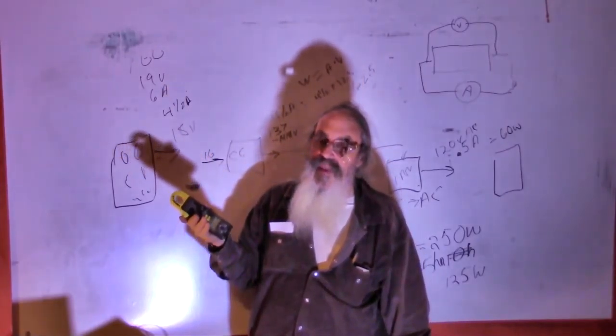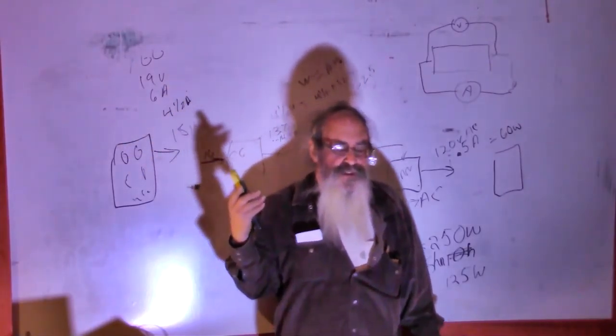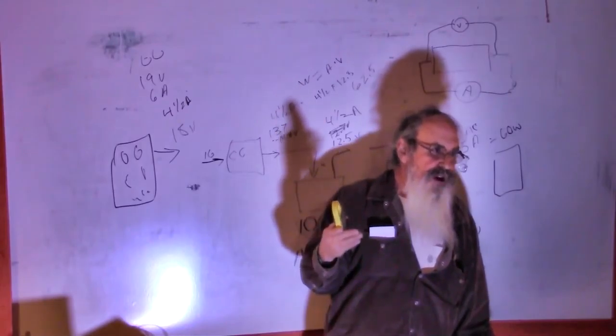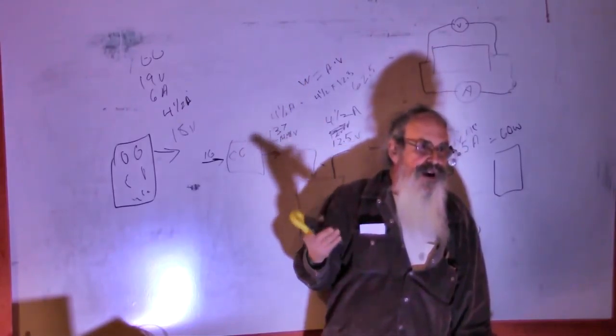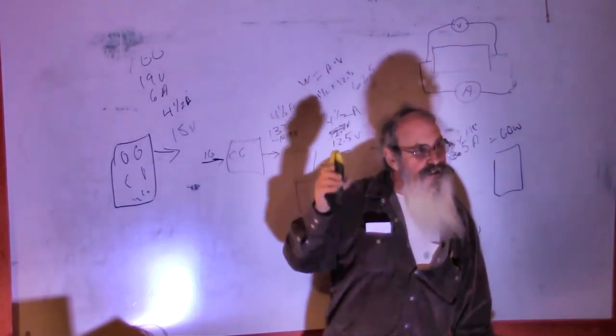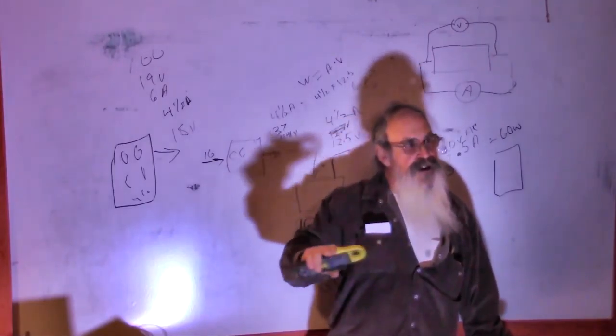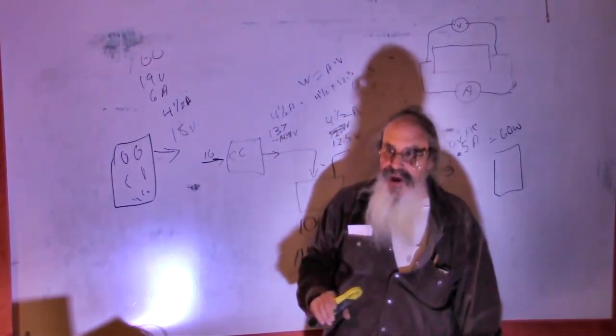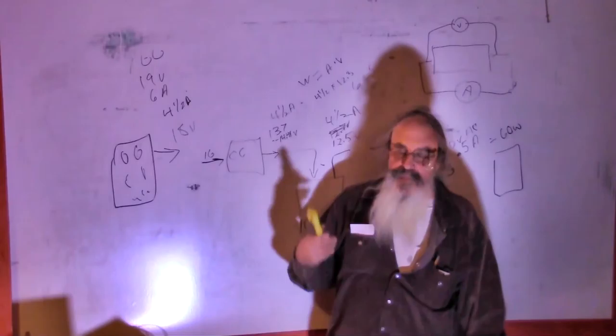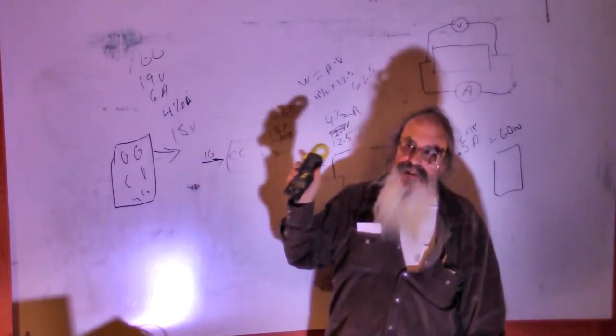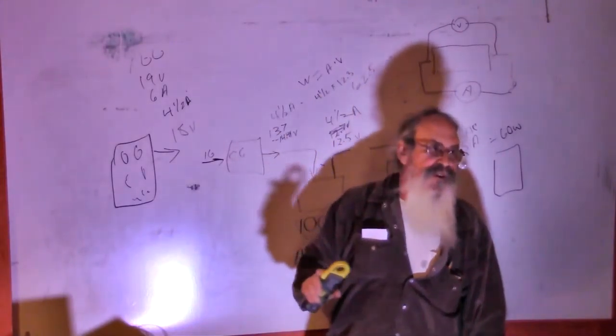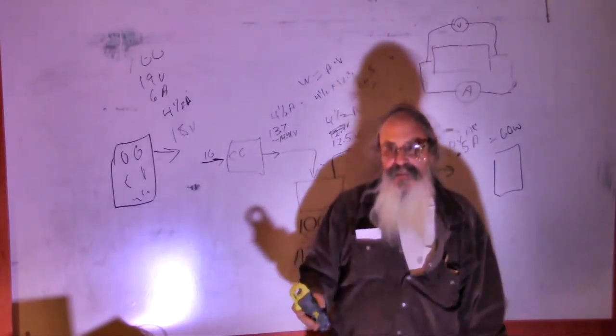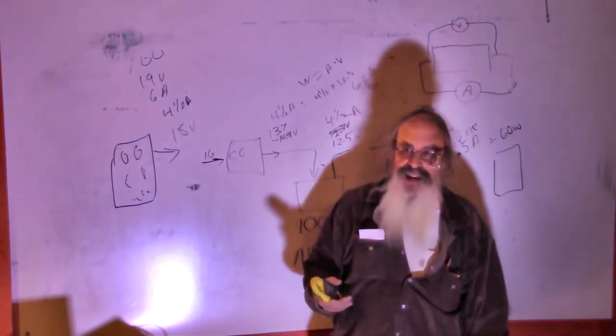I don't know if anybody has ever installed a swamp cooler motor - they say adjust the pulley so it's drawing the number of amps specified on the nameplate of the motor. Nobody in the world ever does that except maybe me, and this is the meter you need to do it with, because you clamp it over the wire, adjust the pulley, turn it back on, and see how many amps you're drawing.